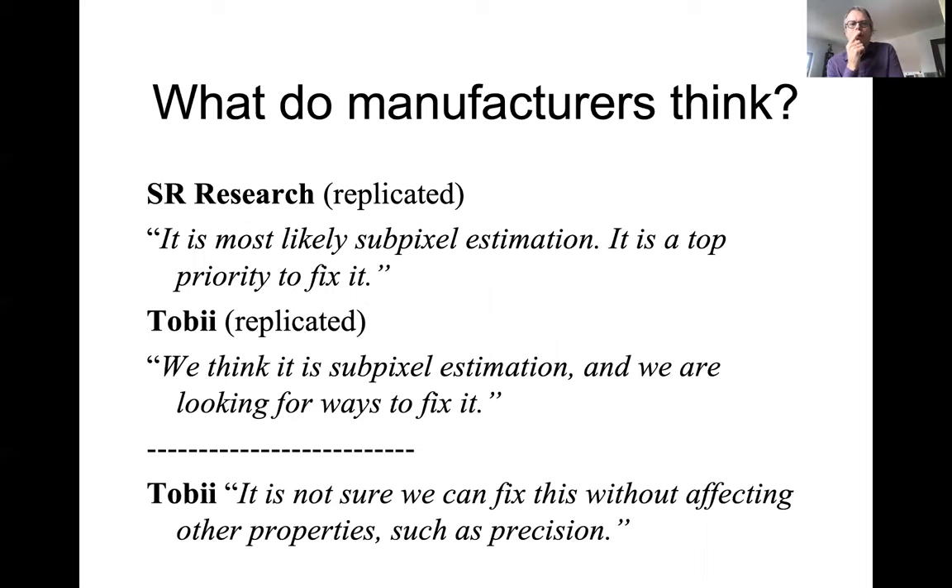Once I had these results, I talked with the manufacturers. SR Research built their own stepper box and replicated the amplitude errors. They said it's most likely sub-pixel estimation and they want to fix it. Tobii borrowed our stepper box, also identified it as a sub-pixel estimation problem, and are looking for ways to fix it. Interestingly, Tobii also said they're not sure it can be fixed without affecting other properties such as precision. I'm not even sure it can be fixed — I think the problem is really difficult.